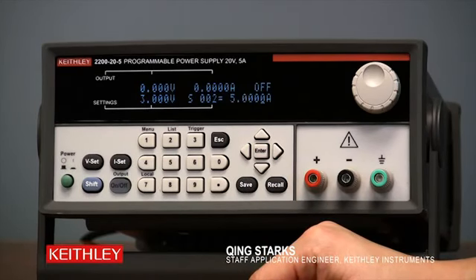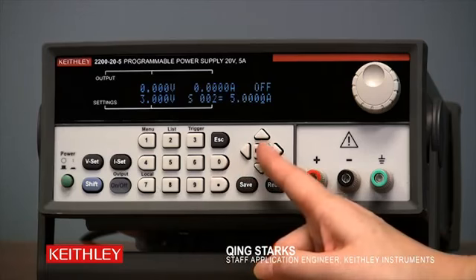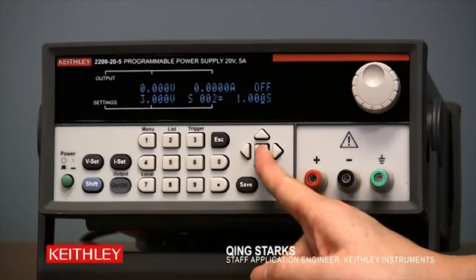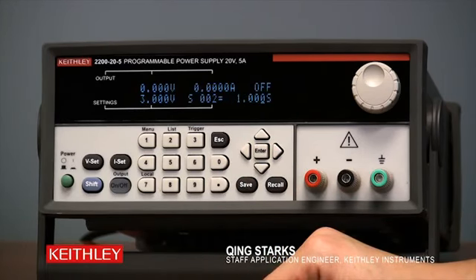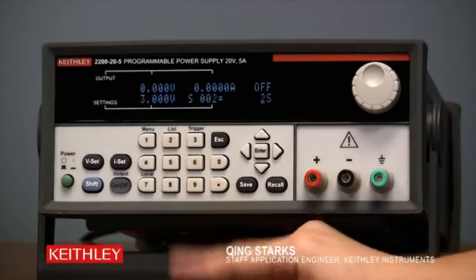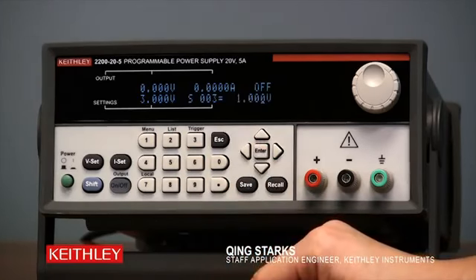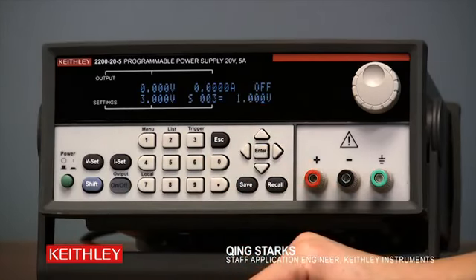The current limit now is at 5 amps, and we're happy. We'll just press Enter. The time duration is 1 second. We can change that to 2 seconds by pressing 2, Enter, and the display will shift you to the next step, which is step 3.